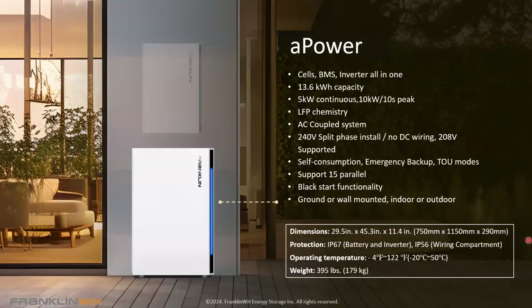And then I did answer one other question, but I just want to make it clear to the group. It was unclear how many loads the aGate would be able to support. It's 200 amp rated, meaning we can move up to 200 amps worth of circuits behind the MID, accomplishing a whole home backup for a 200 amp residential service or less. However, the capacity of the generation sources is what's going to limit what you can actually back up, meaning it would be a combination of the PV output as well as the ESS output to meet specific load. For example, if you had 10 kilowatts of PV and 1 aPower X, you're going to be hovering around 15 kilowatts of power available for those loads.